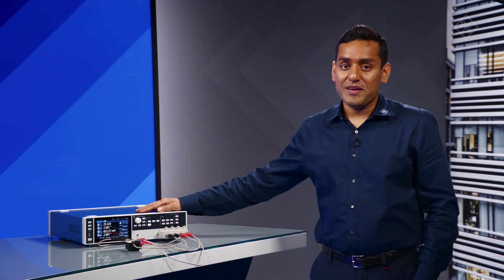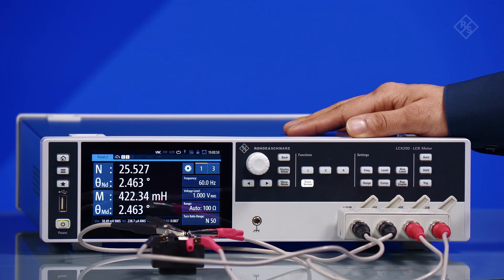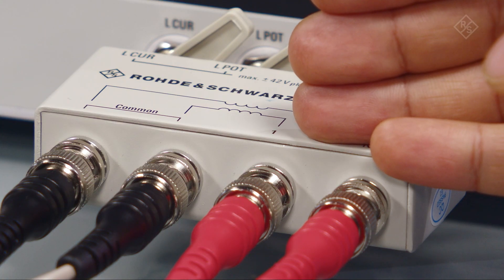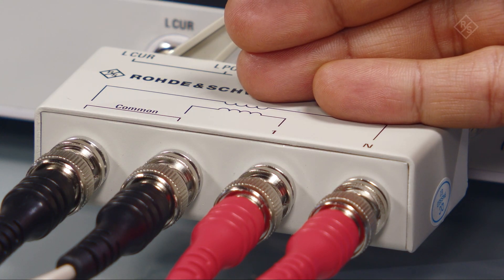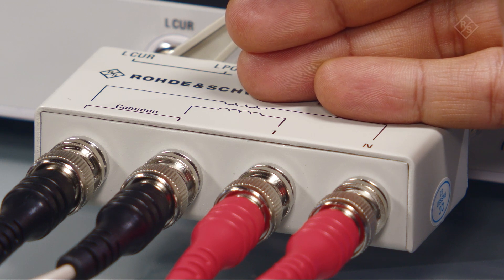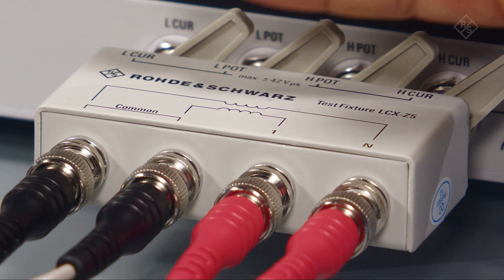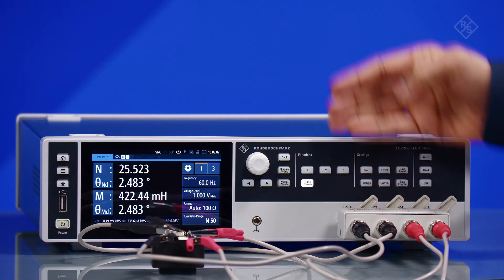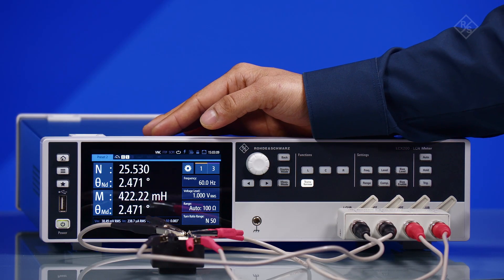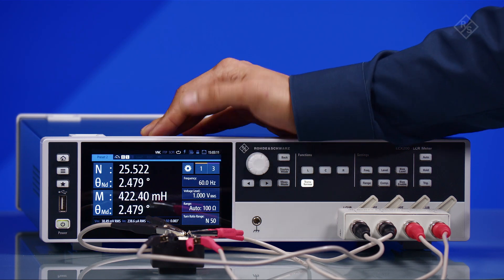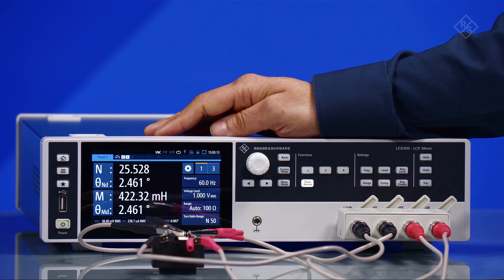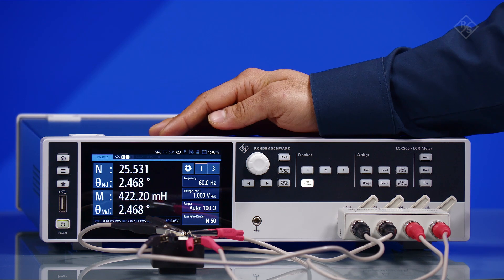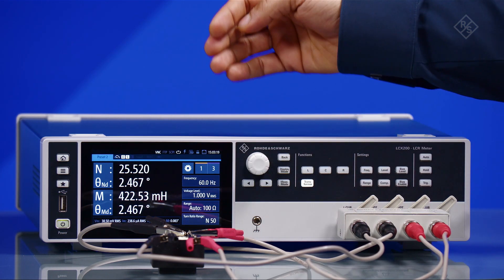Before starting the measurement, please make sure that the test leads with the red alligator clips are connected to the N and 1 connections, and the test leads with the black clips are connected to the outer and the inner common connectors. Set the operating frequency to the desired main frequency of the transformer, which is 60 Hz in our case. Set the test signal level to one volt and the impedance range to auto.